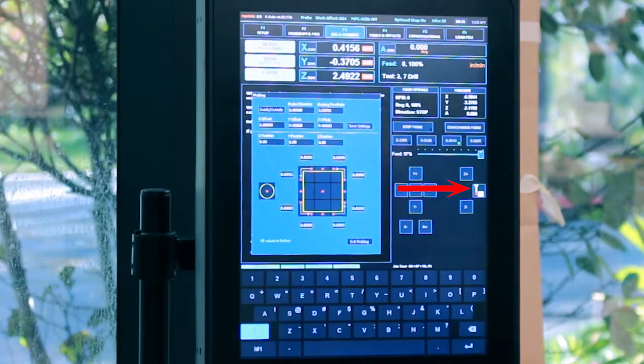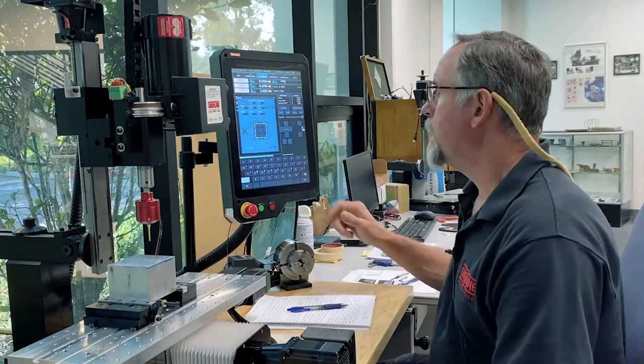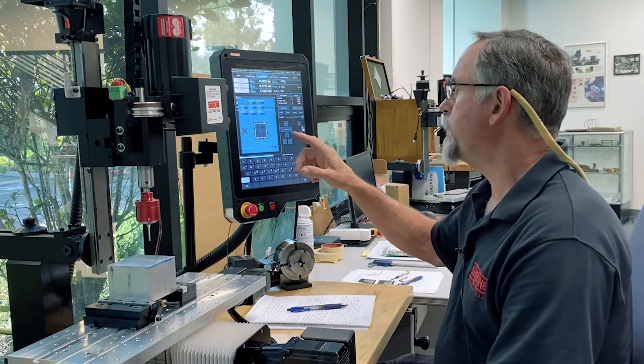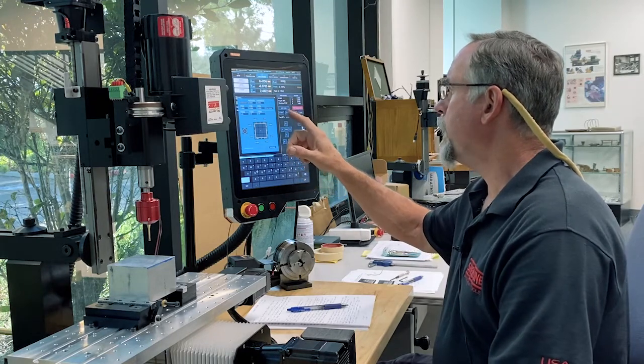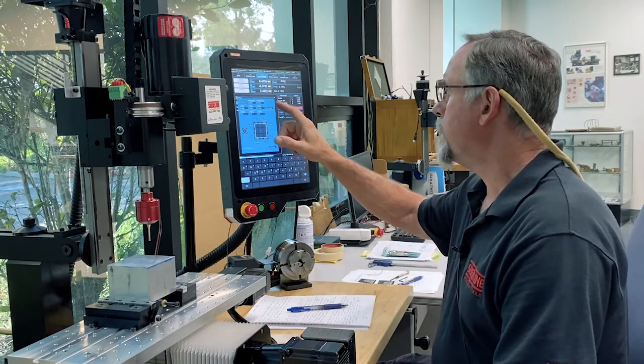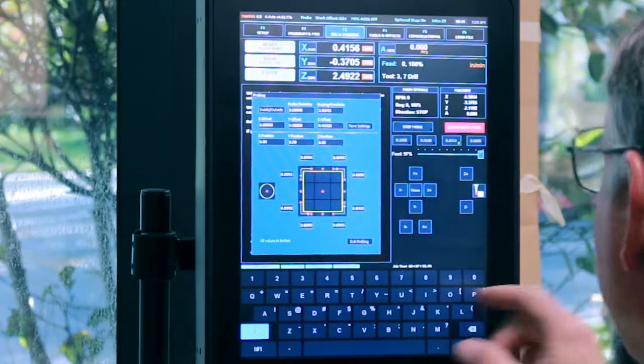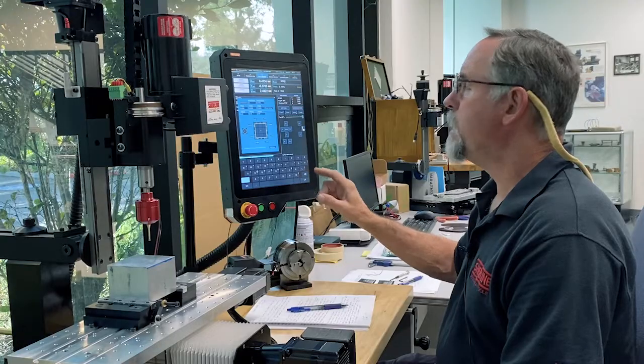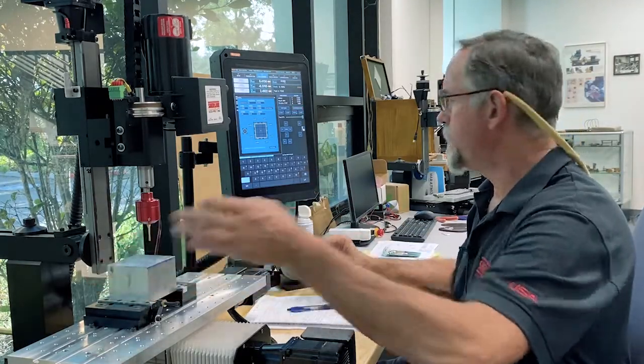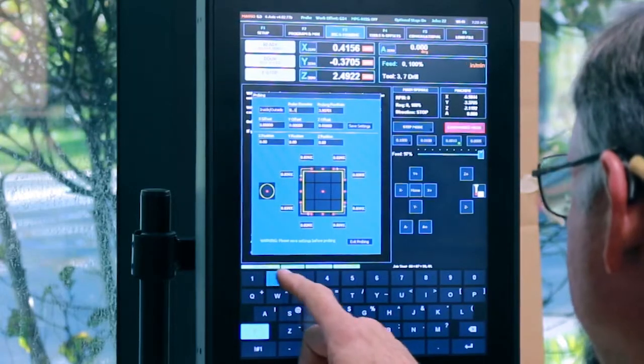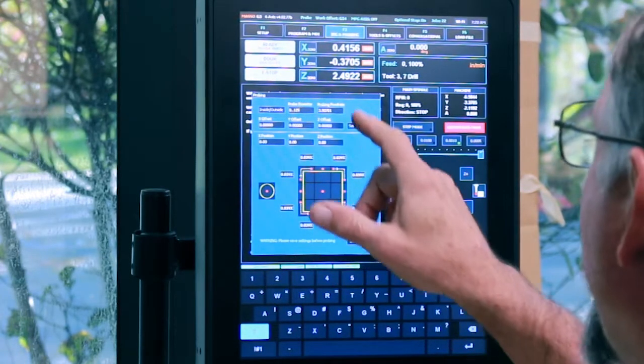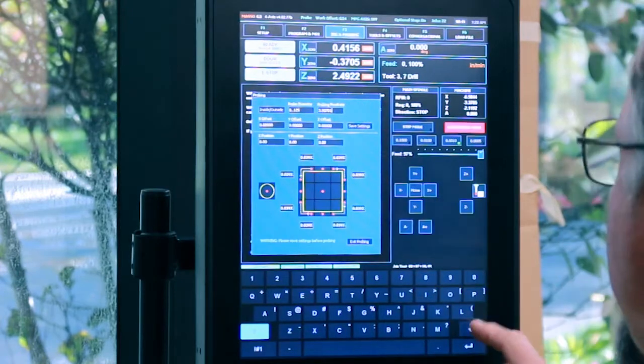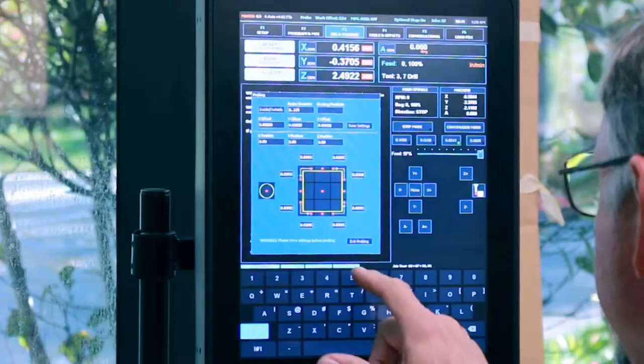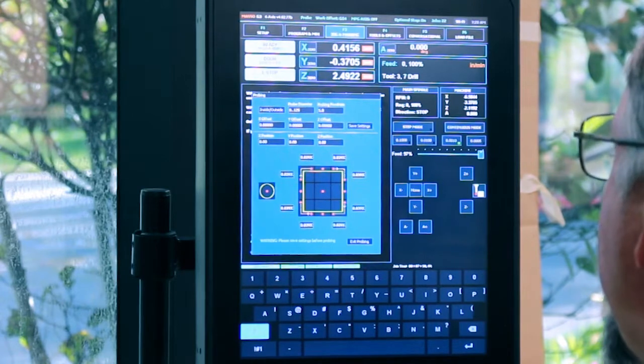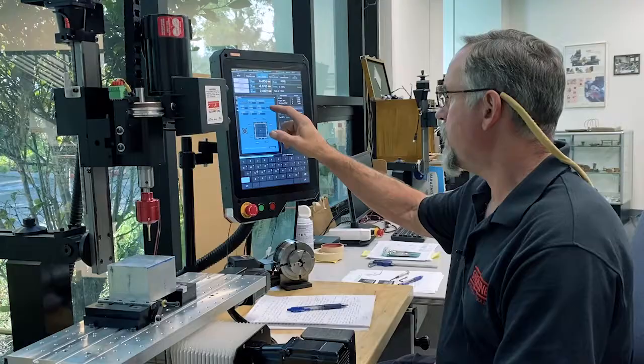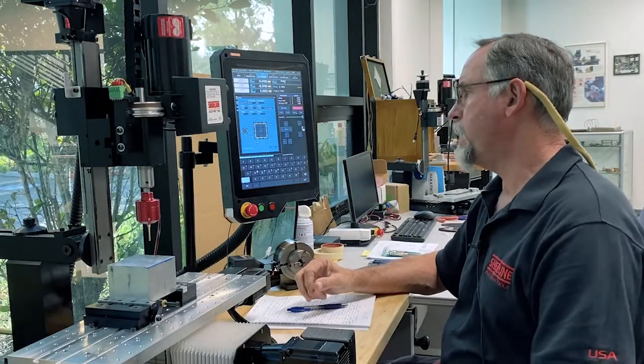On the settings we have probe diameter, so I'm going to punch that in—this is a 1/8 inch ball, so 0.125. Then probing feed rate—we're going to go with the same 5 inches a minute, 5.0. Then I just click Save Settings, so those settings are saved.